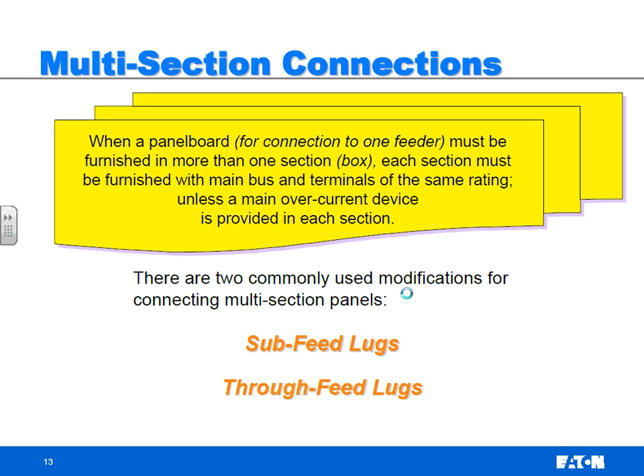Many times you will get into the need for multiple panelboard sections. When a panelboard must be furnished in more than one section or more than one box, each box must be furnished with the main bus and terminals of the same rating unless a main breaker is in each section. Panelboards come in certain chassis configurations, whether it's 18 circuits, 30 circuits, or 42 circuits, and that tells you how many poles you can put in there for feeder breakers. Up until 2008, 42 circuits was the largest that the NEC would allow in a panelboard. In any state that has adopted the 2008 or newer NEC, that 42 circuit restriction is gone.